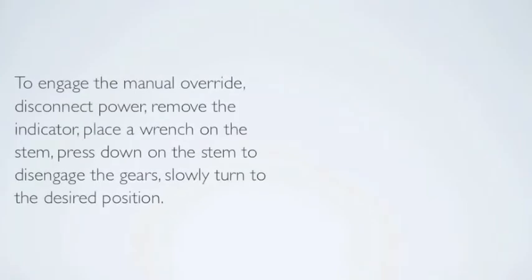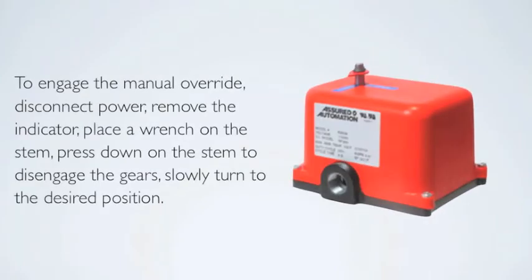To engage the manual override, disconnect power, remove the indicator, place a wrench on the stem, press down on the stem to disengage the gears, and slowly turn to the desired position.